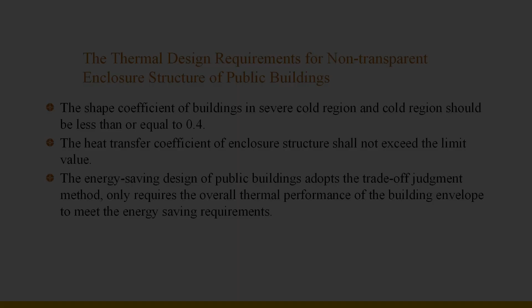The thermal design requirements for the non-transparent enclosure structure of public buildings are: 1. The shape coefficient of buildings in severe cold and cold regions should be less than or equal to 0.4. 2. The heat transfer coefficient of the enclosure structure should not exceed the limit value in certain climatic zones. Because public buildings focus on building facade and function, sometimes it is difficult to fully meet the heat transfer coefficient limit. The energy saving design of public buildings adopts the trade-off judgment method.